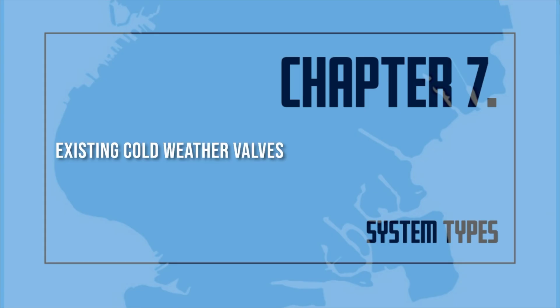Existing cold weather valves. An automatic sprinkler system should not be shut off and drained to avoid freezing during cold weather. However, parts of the sprinkler system may be shut down. Permission must be obtained from the local firehouse. Permission may be given to shut off a maximum of 10 sprinkler heads on a wet pipe system. These shut-off valves are commonly referred to as cold weather valves. These valves are no longer permitted to be installed.